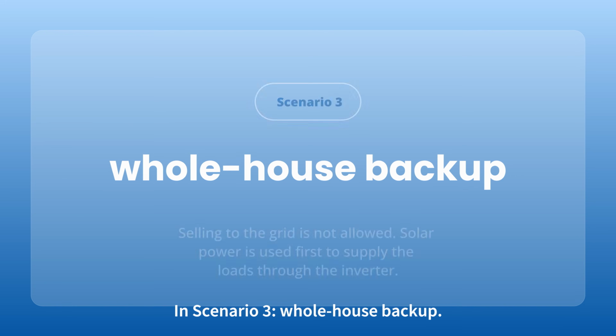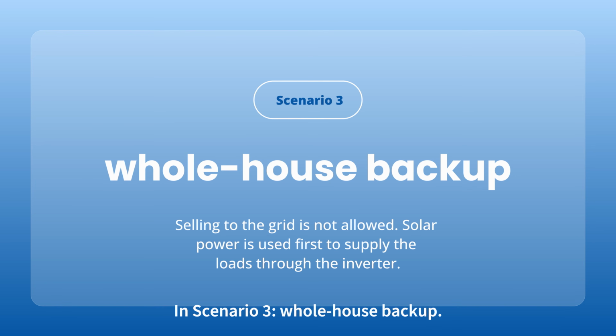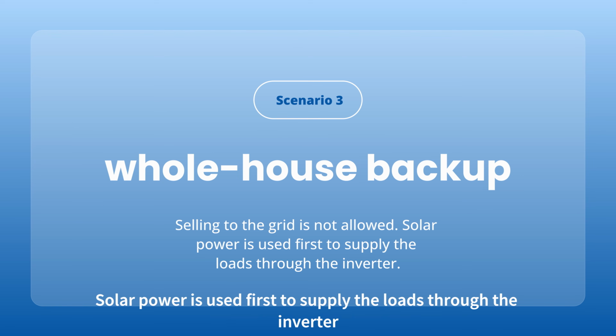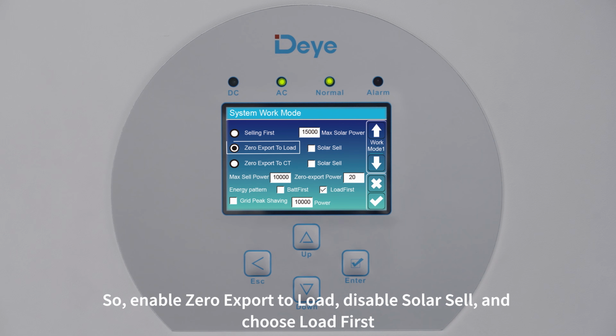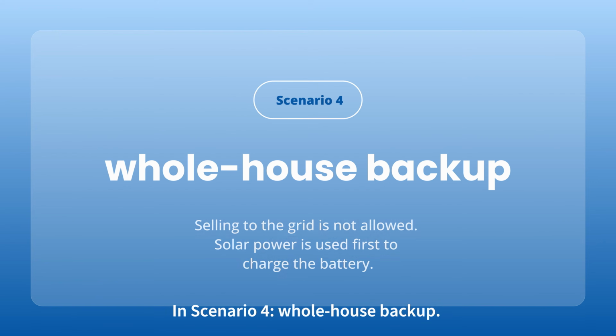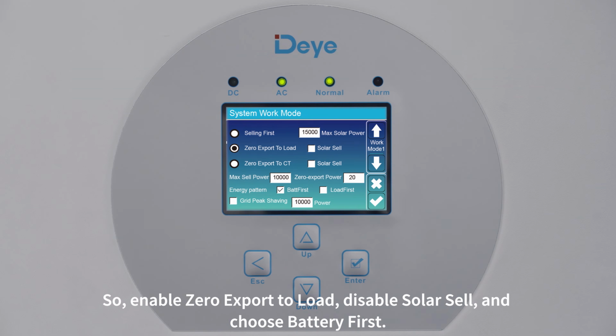In scenario 3, whole house backup. Selling to the grid is not allowed. Solar power is used first to supply the loads through the inverter. So, enable zero export to load, disable solar sell, and choose load first. In scenario 4, whole house backup. Selling to the grid is not allowed. Solar power is used first to charge the battery. So, enable zero export to load, disable solar sell, and choose battery first.